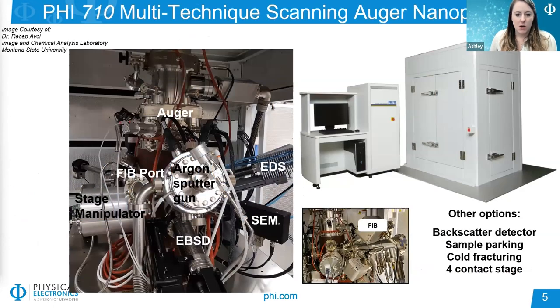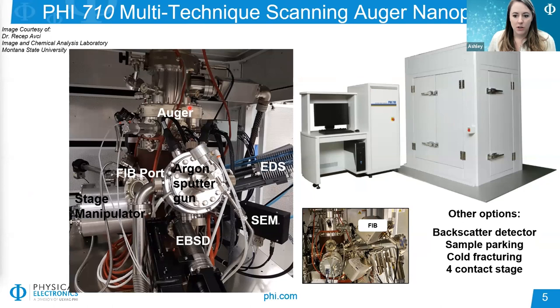At Physical Electronics, our latest model of Auger instrument is the 710 multi-technique scanning Auger Nano Probe. The instrument has an acoustic enclosure which serves as a vibration isolator. Inside, the main feature is the field emission electron source and Auger electron analyzer at the top. It points straight down, normal to the sample surface, and because we have the primary electrons and the analytical signal on the same axis, you can get true line-of-sight vision to the surface with no shadowing, making it ideal for highly topographical samples such as those made in 3D printing.